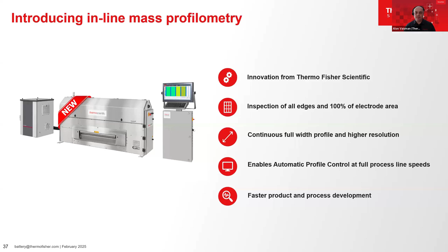To help visualize the difference between the conventional single-point scanning gauges and the mass profilometer, we can use the illustration on this slide. A scanning gauge usually consists of a frame on which a sensor moves from one side of the electrode foil to the other and repeats. The resulting dataset captures sort of a zigzag pattern across the electrode as the coated foil moves through the process.